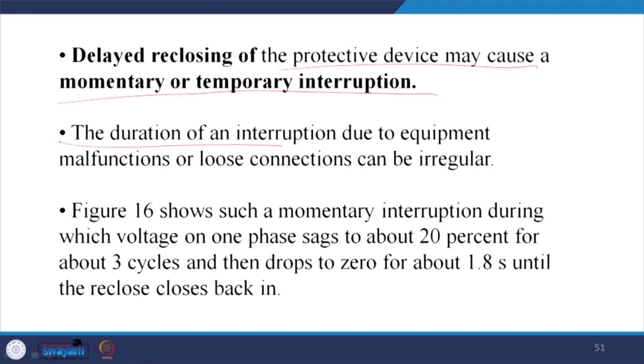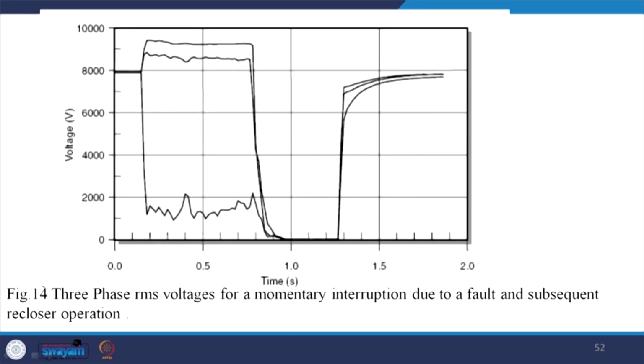The duration of an interruption due to equipment malfunction or a loose connection can follow an irregular pattern. You can see this very frequently, and Figure 16 shows the momentary interruption that I am showing here. This is the voltage, and all of a sudden it drops for the interruption, and then it picks up again. This is the three-phase RMS voltage, a momentary interruption due to a fault and a subsequent recloser operation, and this is the duration of the interruption.